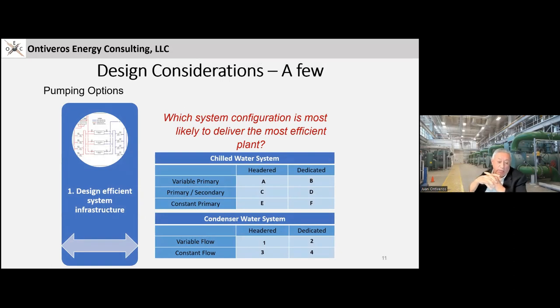Another one is pumping. You want to design your system so you don't build constraints into it from the very beginning. This is just like a chilled water system. There are various options. You can do variable primary, primary secondary, or constant primary, and maybe headered, in other words, four pumps serving all four chillers. Dedicated means one pump serving one chiller. There are challenges with that. Same thing with a condenser water system: variable flow or constant flow, whether it's headered or dedicated. In my opinion, the most efficient is variable primary and variable flow. It allows you to take advantage of optimization to the best advantage.